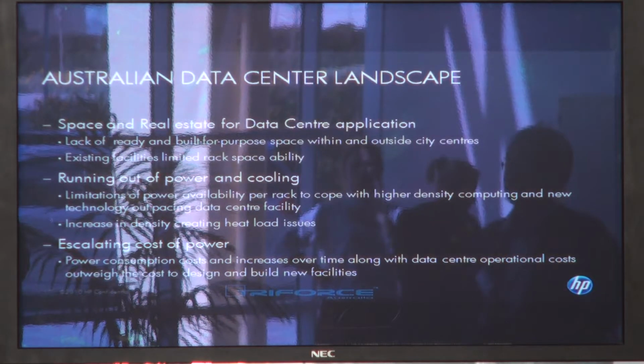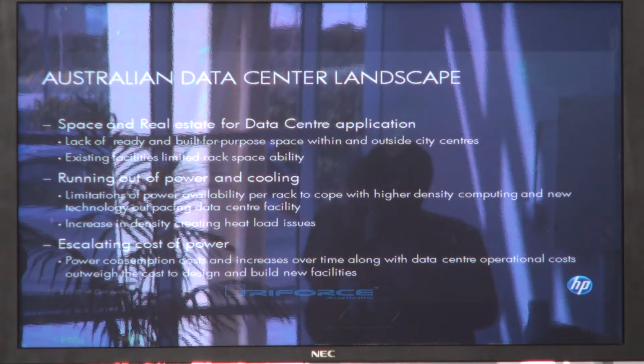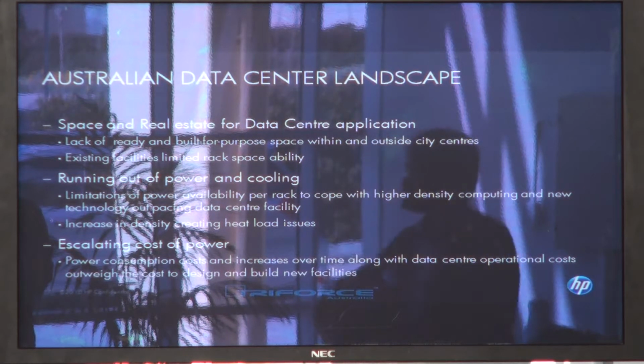Power and cooling, the common thing we're talking about here is the PUE rating. As Steve and Chris mentioned, we've also seen between 2 and 2.5 PUE rating on most of the data centers we work within. Some of the issues we have around that are not just cooling, but power, especially around CBD areas. It's very public that Sydney lost power, I think, 3 times last year, the CBD itself.